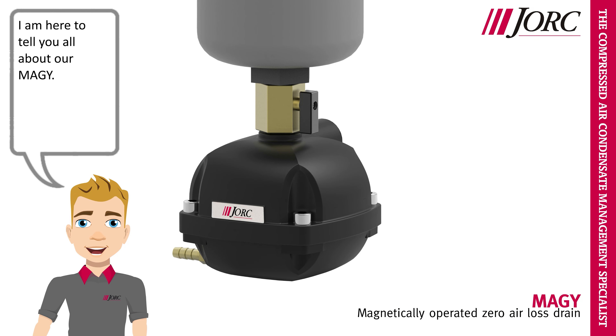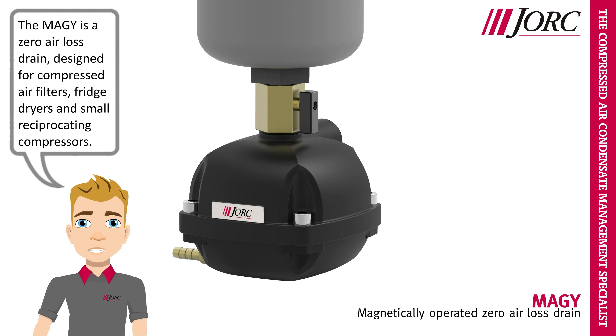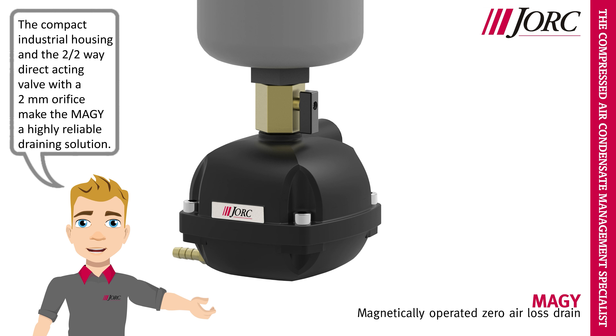Hi, I am Yorick, and I am here to tell you all about our MAGY. The MAGY is a zero air loss drain, designed for compressed air filters, fridge dryers and small reciprocating compressors. The compact industrial housing and the two two-way direct acting valve with a 2mm orifice make the MAGY a highly reliable draining solution.